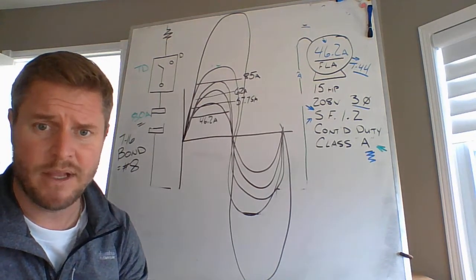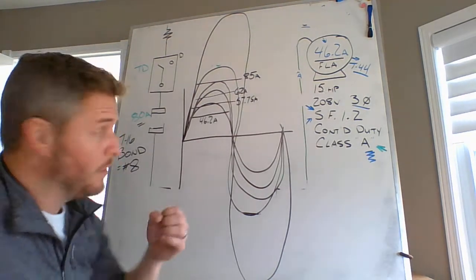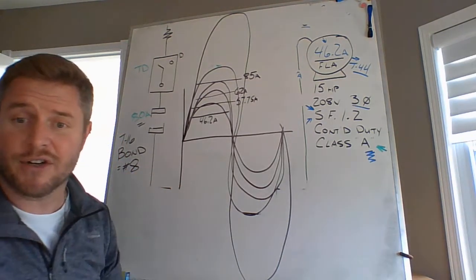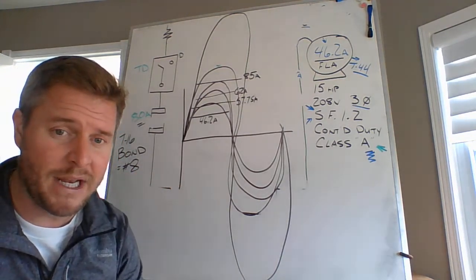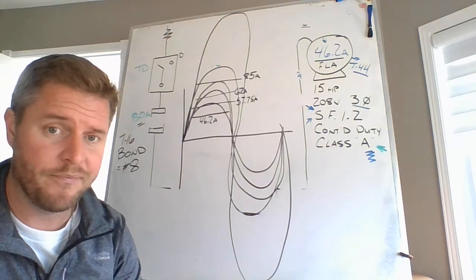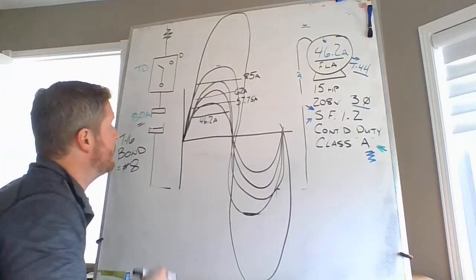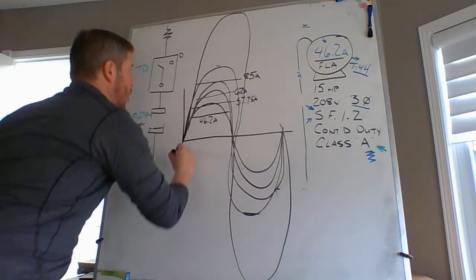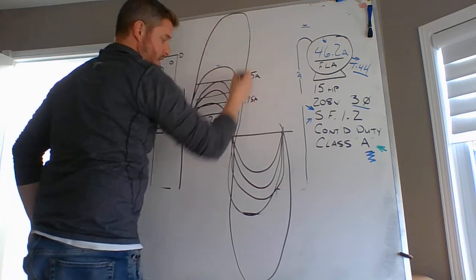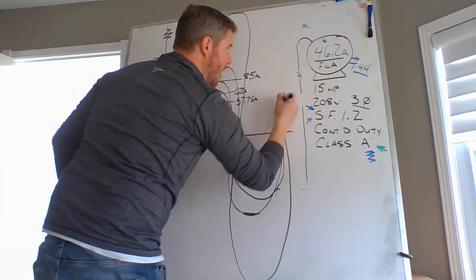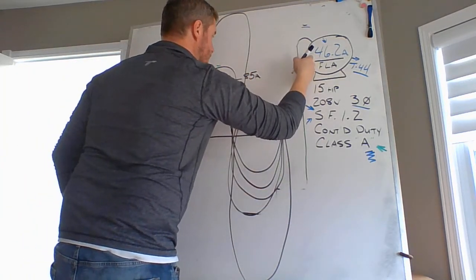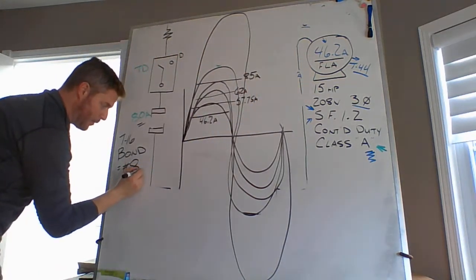amps flowing. And if it's a dead short and you installed number 8 as a bonding conductor, that provides a very low impedance path back to ground, which means there's going to be an exponential amount of current that flows to this motor on your number 6 conductors and returns on your number 8 bond.